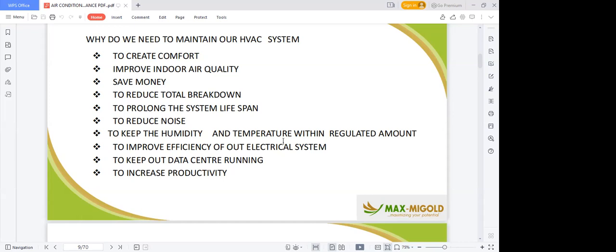And those of us that have the capacity to maintain a server system within a building, if you go into your server room, you see they are very cold, they are chilly. All the equipment needs to be cooled down, because if they are not cooled down, some company can actually run off your customers. Somebody wants to withdraw, but because there's no AC, the units are getting so hot they have to shut down. So people who want to make withdrawals, if you are in the bank, it starts affecting. If there's no AC in the server room, you know what happens. The base station goes off, so people within that location cannot make calls. So your AC is a vital component of your environment.